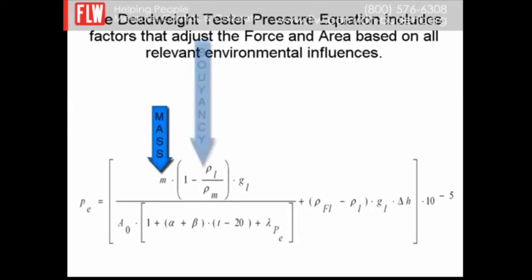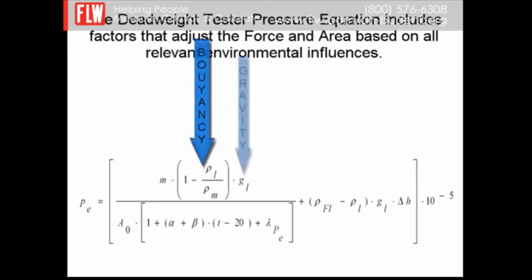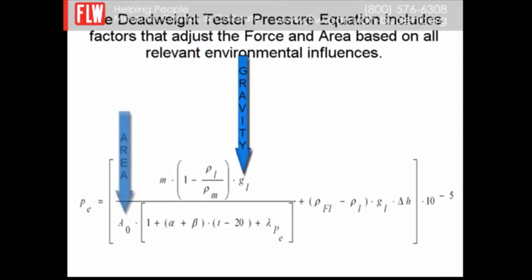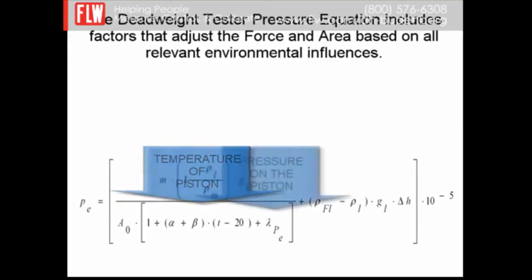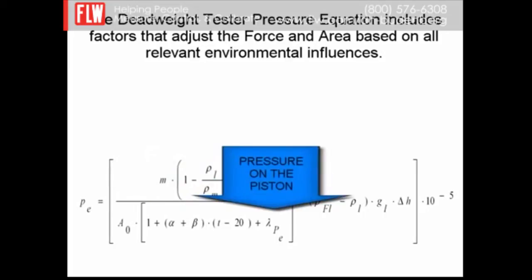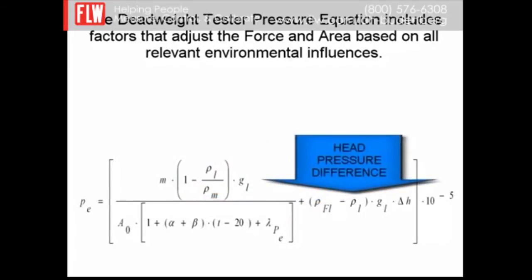These factors include mass, buoyancy, gravity, area of the piston, temperature of the piston, pressure on the piston, and even an adjustment for the head pressure difference between the device under test and the dead weight tester.